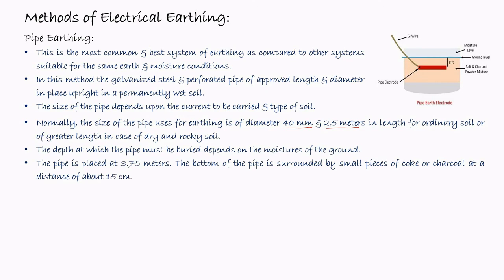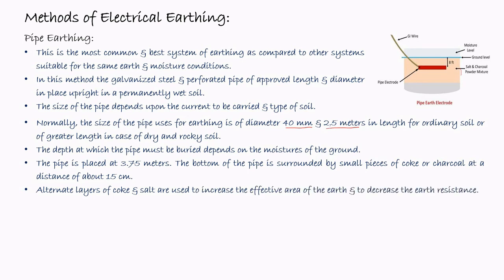The bottom of the pipe is surrounded by small pieces of coke or charcoal at a distance of about 15 centimeter. Here we can see the pipe is placed around 8 feet below the ground, and in this area a salt and charcoal powder mixture is placed. This is basically used to reduce the resistance and increase the conductivity. The alternate layers of coke and salt are used to increase the effective area of the earth and to decrease the resistance of the earth.